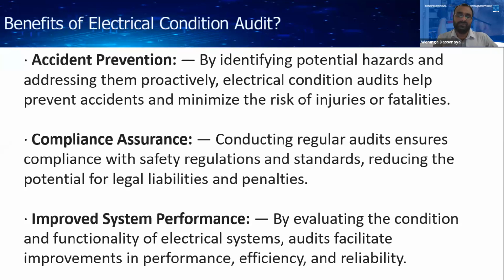That means if your electrical system is not installed correctly, there may be power losses in your system. If you do not use the correct cable size, that cable gets heated, and power is lost as heat due to the cable resistance. So you have to check whether the correct cables and the correct equipment are used in the system. Therefore, if you do a condition audit, identify that kind of failure and rectify it, your system performance can be improved.